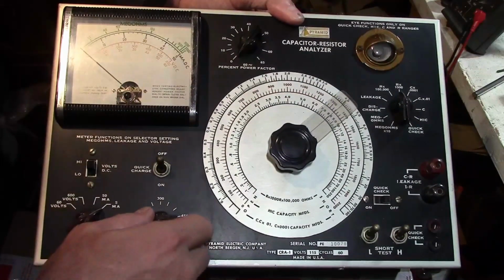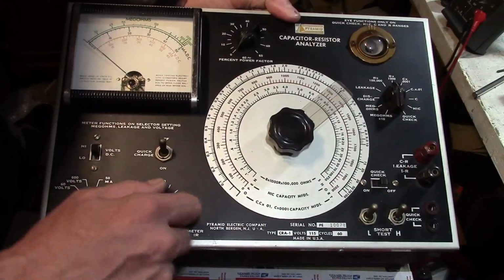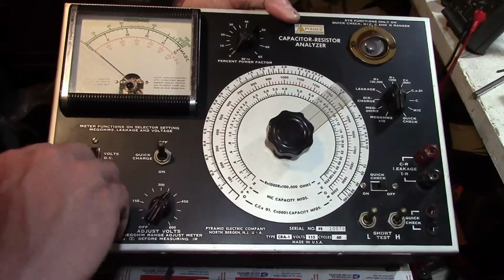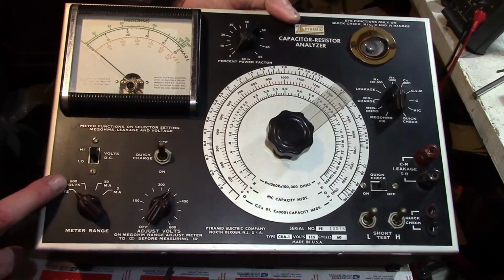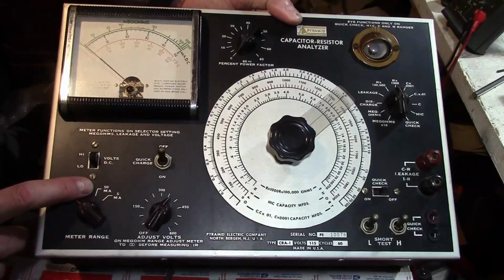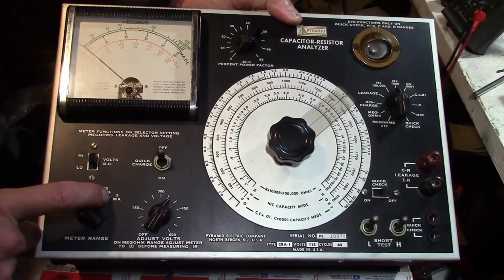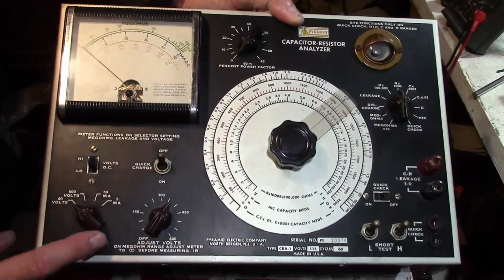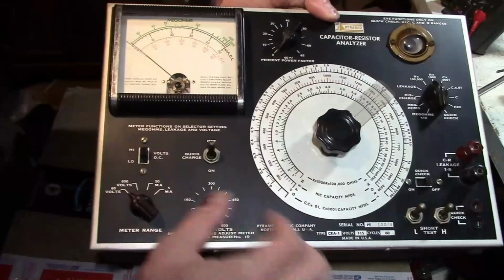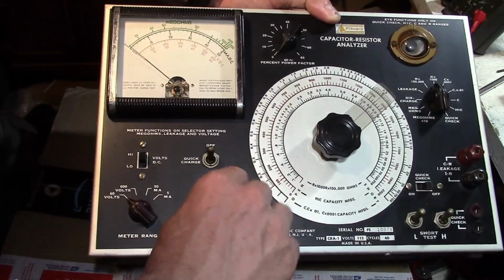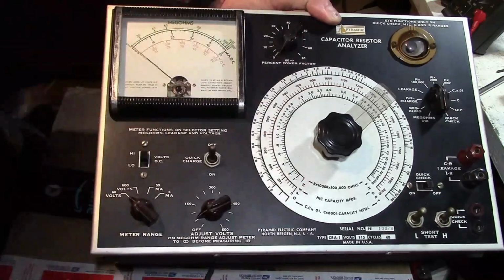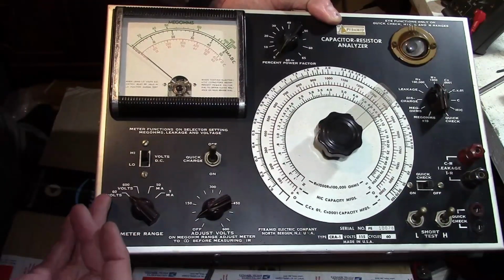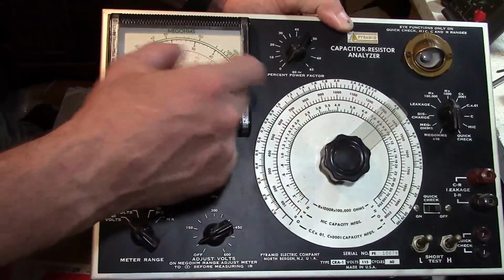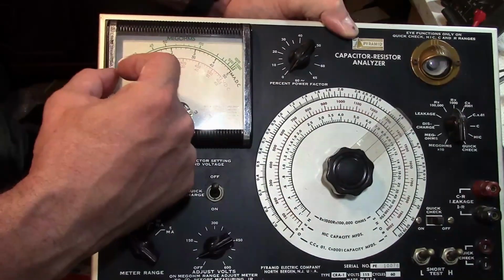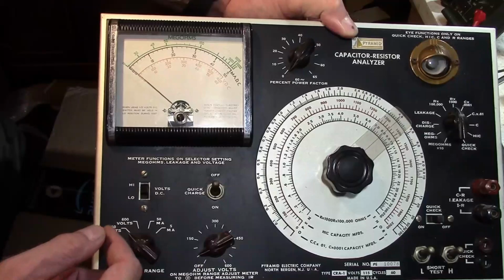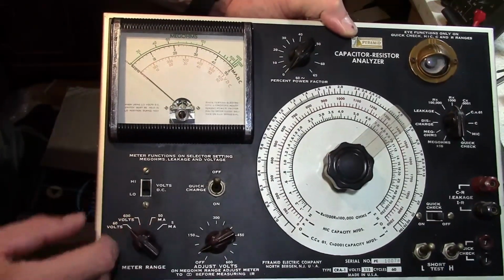So it does go up 0 to 600 volts with this control down here. And it's got two ranges, a 0 to 60 volt range and then a 0 to 600 volt range. Two current ranges, a 50 milliamp, 5 milliamp. I should say those are the meter ranges. It's not the device range. This is the only voltage range control, but I guess is an aid, so when you're testing low voltage caps, instead of having to look on the 600 volt scale and just look at one little narrow section of it, you can drop it down just so it's 60 volts full deflection. Same on the current.